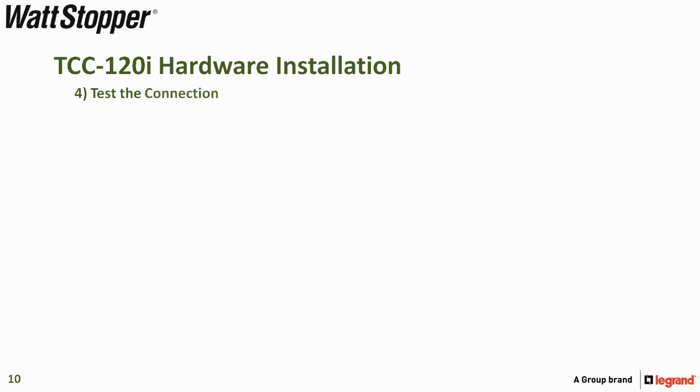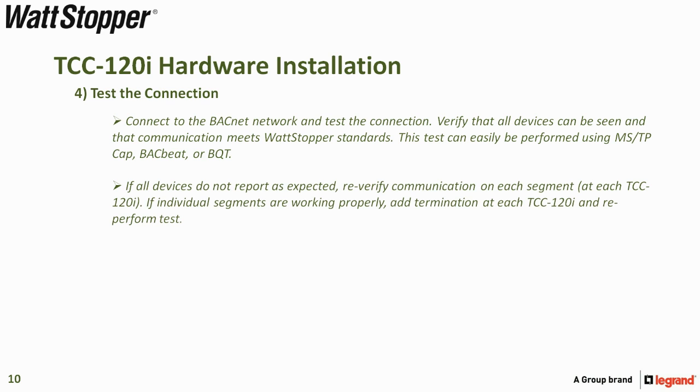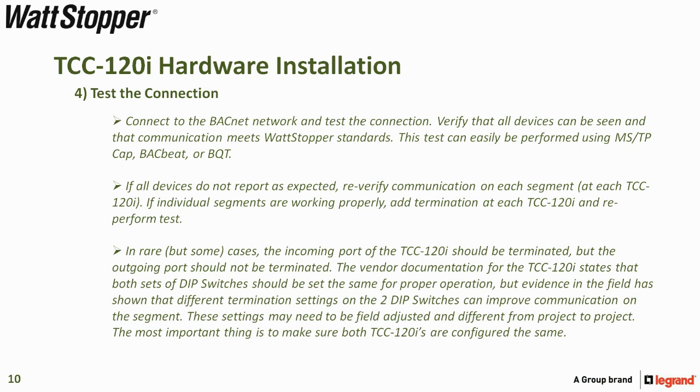The final step is to test the connection. Connect to the BACnet network and verify that all devices can be seen and that communication meets Wattstopper standards. This test can be performed using MSTPCAP, BACbeat, or BQT. If all devices do not report as expected, re-verify communication by separating each segment. If individual segments work properly, add termination at each TCC-120i and re-perform the test. In rare cases, the incoming port of the TCC-120i should be terminated but the outgoing port should not. Field evidence has shown that different termination settings on the DIP switches can improve communication, and these settings may need to be field-adjusted from project to project. Most importantly, make sure both TCC-120is are configured the same.